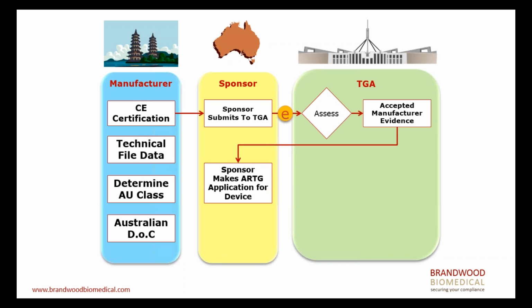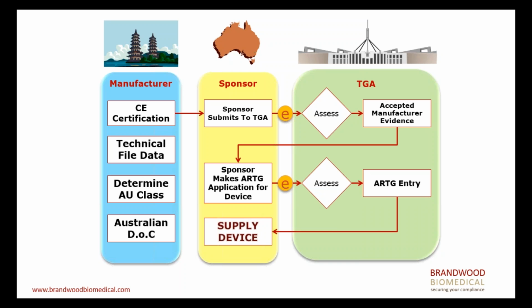Once that's done, the sponsor can then make the ARTG application for inclusion of that device using that manufacturer's evidence. And then again, that's lodged online. It gets assessed by TGA, and if there are no questions and everything looks all good, then we get the ARTG entry, and the sponsor can now legally supply the device in Australia.